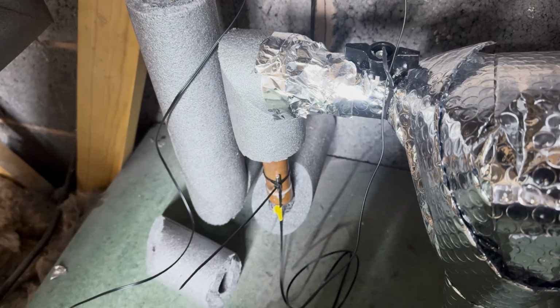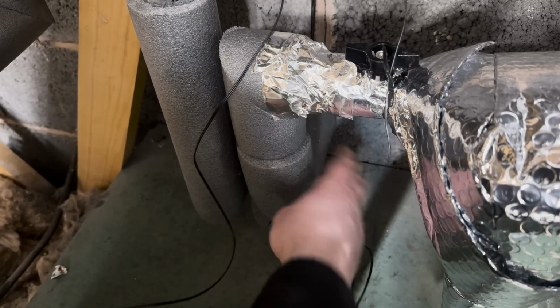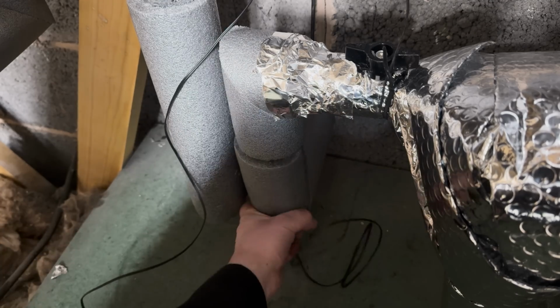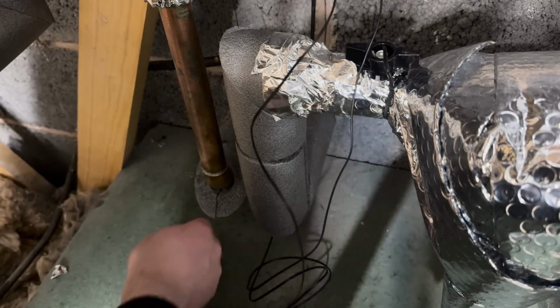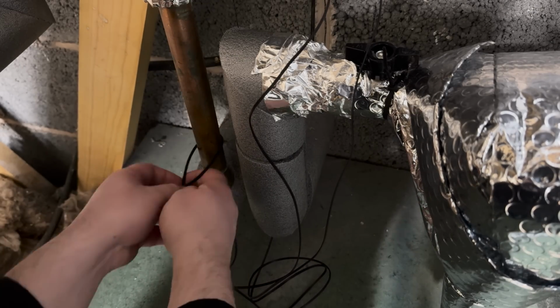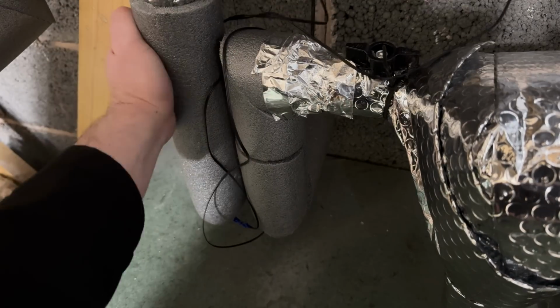Now to get a good reading, I had to do a couple of things. First of all, thermal paste to the end of the probe, and then put that on top of the bare pipe as close to the wall as I could. So I put that on the pipe, I tie wrapped it down so it's nice and tight against that, then I wrap some foil around it and then put the insulation over the top. This should give me the best reading I possibly can from those temperature probes without them obviously being inside the flow of water like a proper heat meter or ultrasonic device would do.